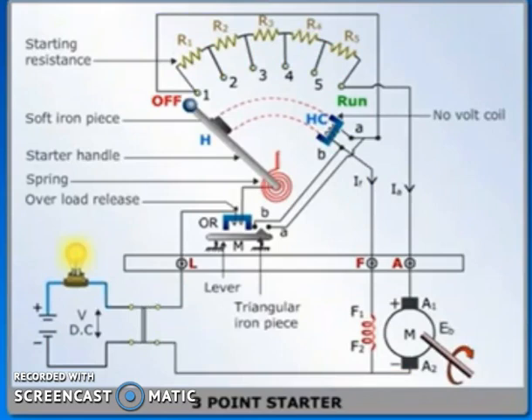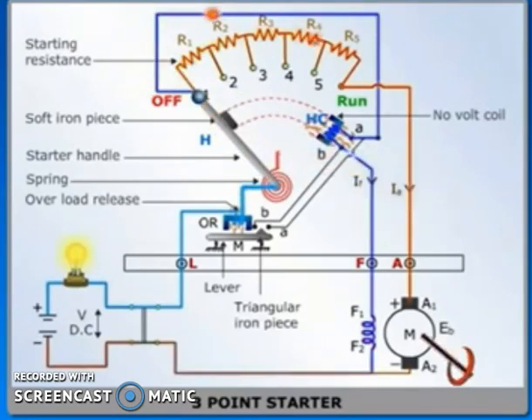Now assume the handle H touches stud one. The shunt field and the holding coil HC get connected in series across the supply, whereas the armature gets connected in series with the entire starting resistance. Current begins to flow in both field and armature windings, and the motor starts rotating.